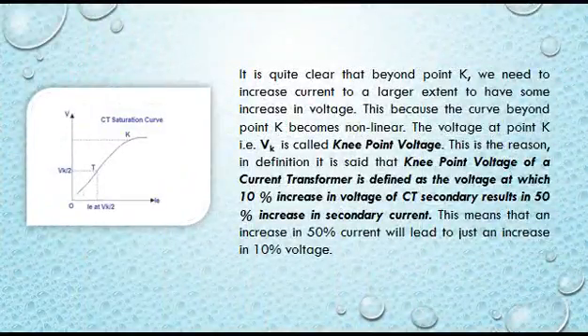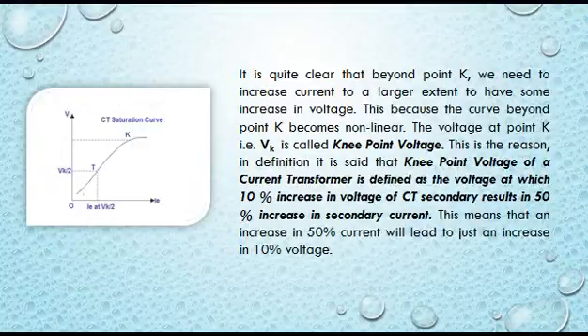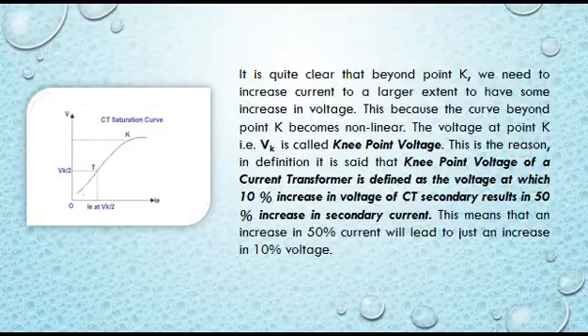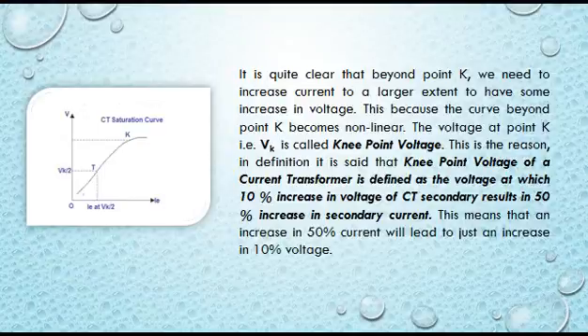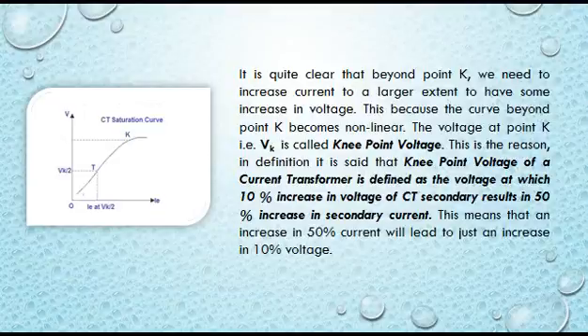Carefully observe the CT saturation curve. You can see that up to point K the curve is linear, while after K the curve becomes nonlinear. Beyond point K, we need to increase the current to a larger extent to achieve some increase in voltage. The voltage at point K is indicated as VK and is called the knee point voltage.